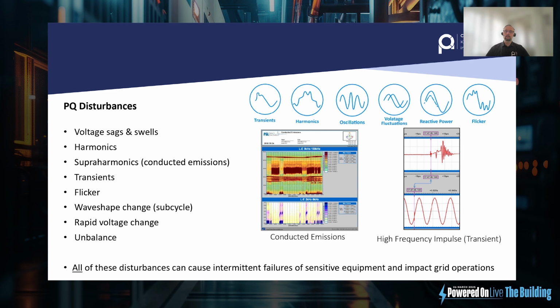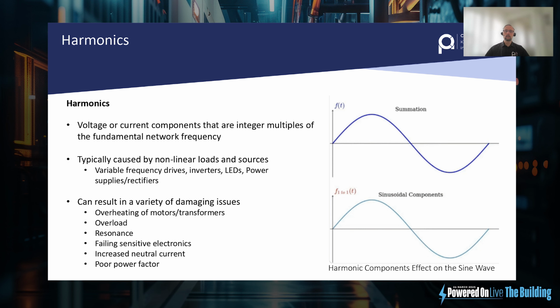So if we look at the disturbances I mentioned before, we've got transients, harmonics, oscillations, voltage fluctuations, reactive power, flicker compensation. Well, not flicker compensation, sorry, flicker, which is affecting the lights and other equipment. Ultimately, rapid voltage changes and so on. These are all things that affect your equipment and other equipment on site. The more sensitive the equipment is, the bigger the effects these can have on reducing that.